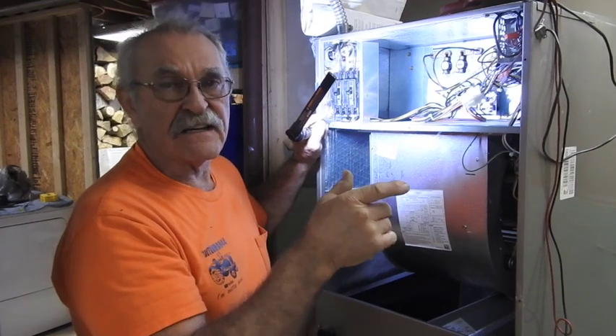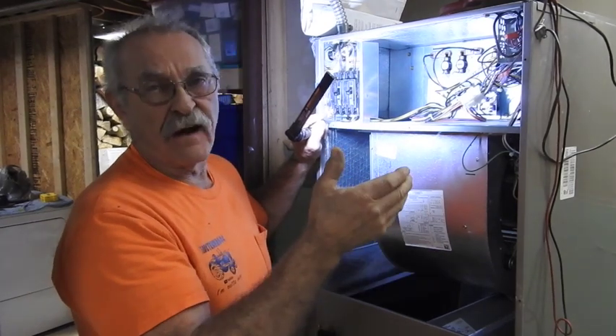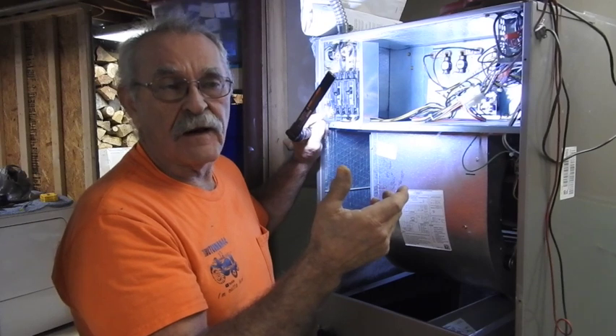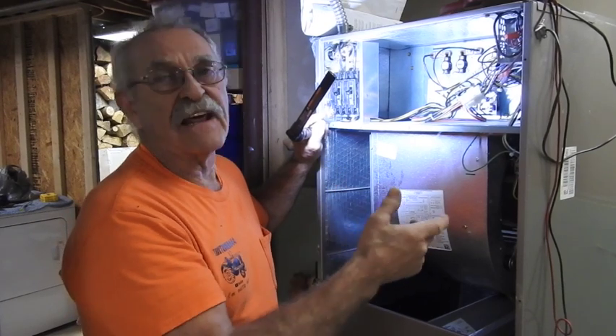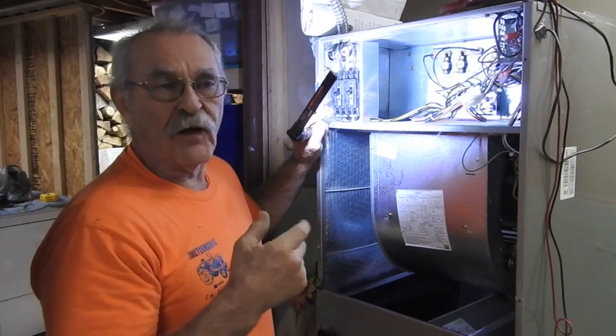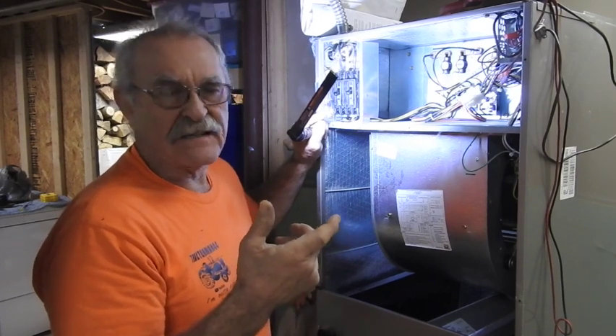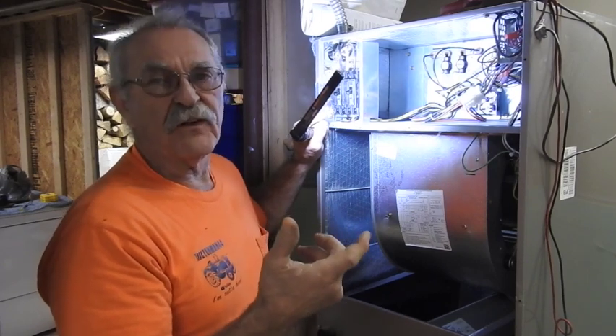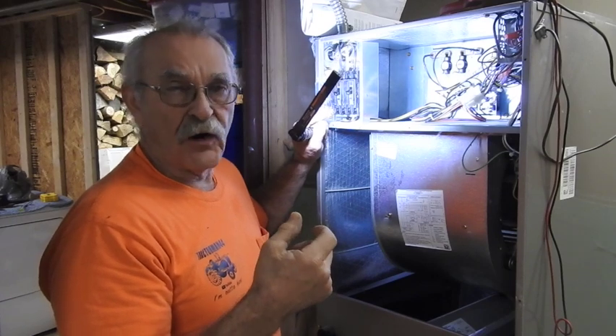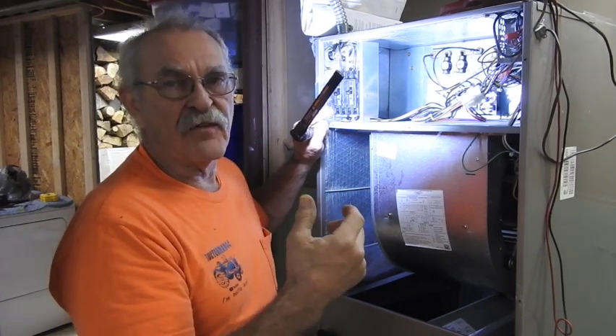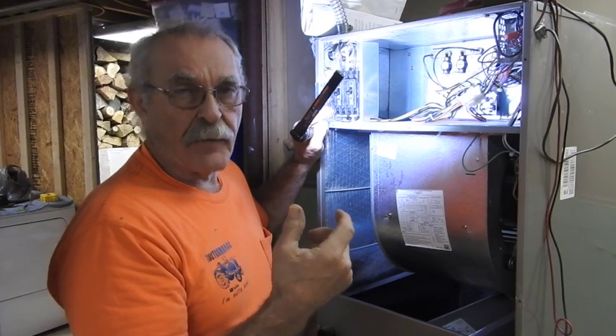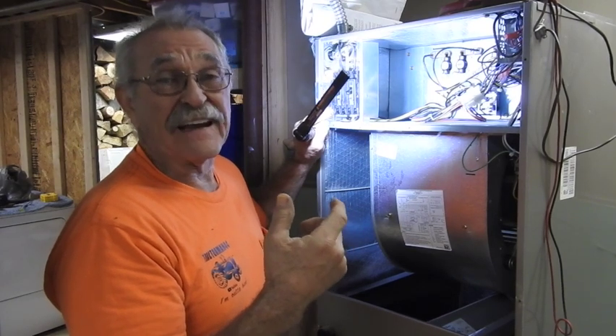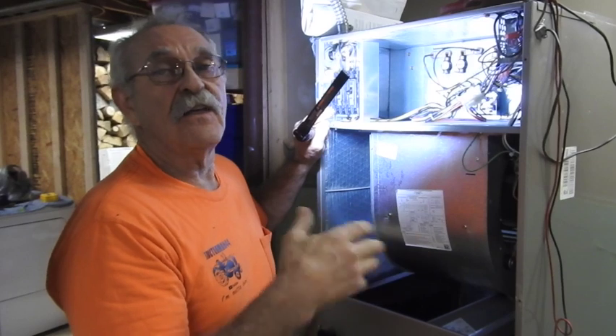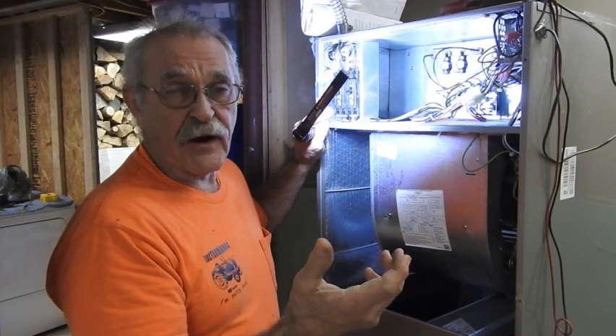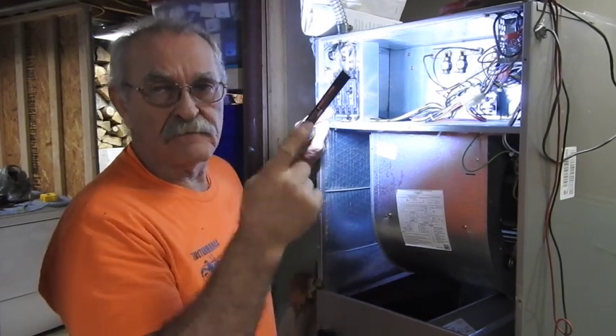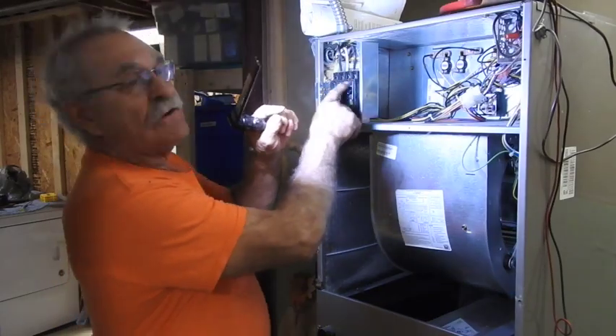So the lower air velocity is going to make the temperature of the air feel a little bit warmer, but it's still going to be the same 53,000 BTUs entering the space. The whole thing about temperature rise has to do with the way it feels when it comes out of the register. A low temperature rise with a real high volume of air is going to feel cold. With a proper amount of air, with a given amount of heat being added to it, the temperature rise is greater and the air feels warm. That makes sense? So at any rate, we're going to go ahead and undo these guys right here.